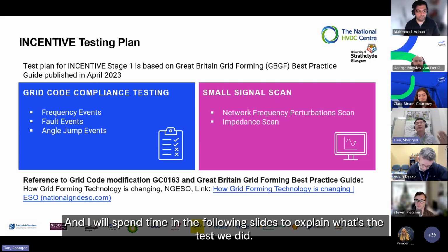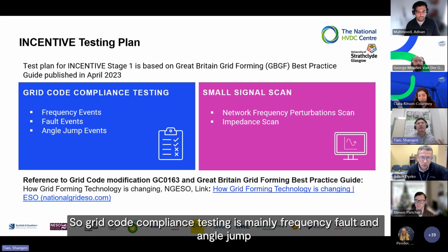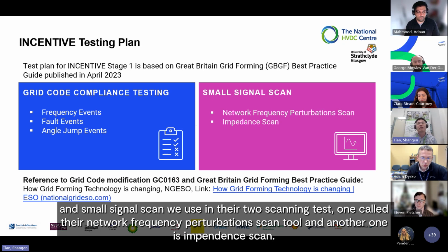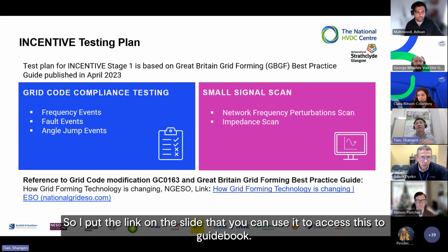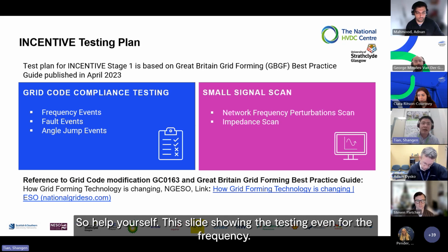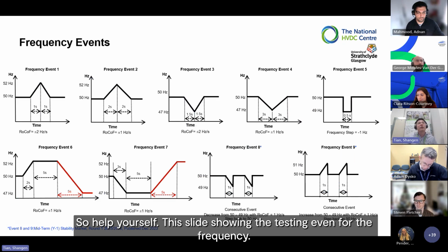I'll spend time on the following slides to explain what tests we did. Grid code compliance testing is mainly frequency, fault, and angle jump. For small signal scan, we use two scanning tools - one called the network frequency perturbations scan tool, and another is impedance scan. I put the link on the slide so you can easily access this guidebook - help yourself. This slide shows the testing event for frequency.